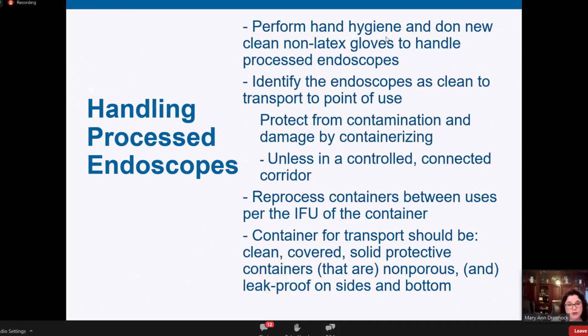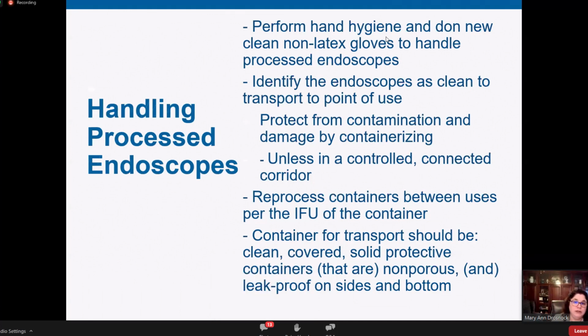So this is your clean transport. And where I often see the breakdown is not with processing staff. They're great about making sure they have gloves on to take the scope out of the AER, dry it and put it into the cabinet. But often when staff comes in to pick that scope up and take it back to the room, that's where I sometimes see the breakdown. So making sure that all staff is aware of handling these with clean gloves from the cabinet on back to the procedure room.